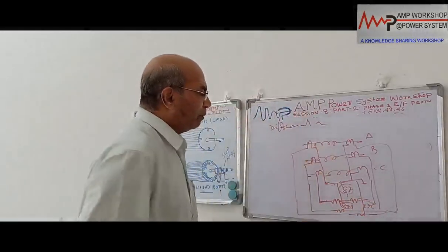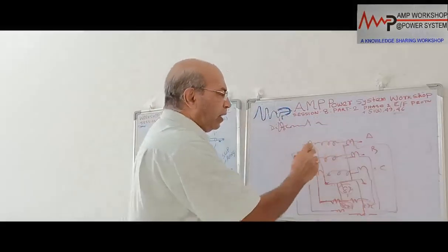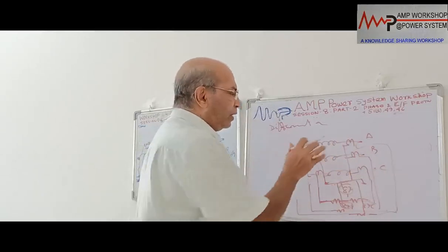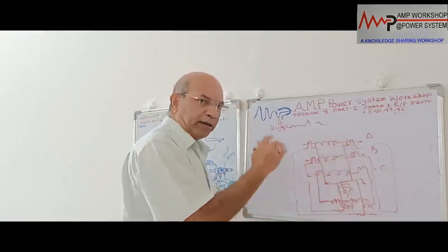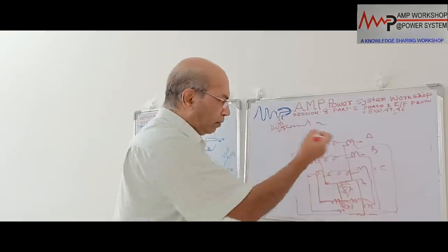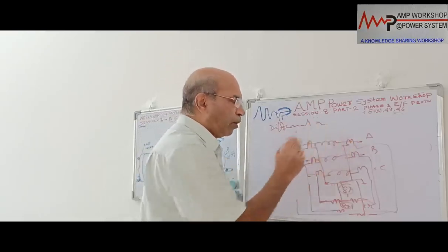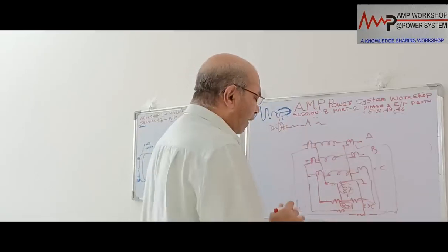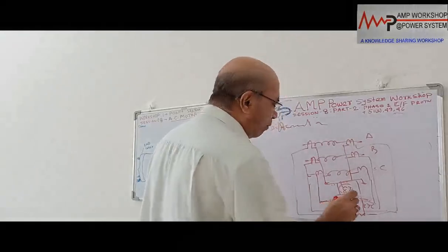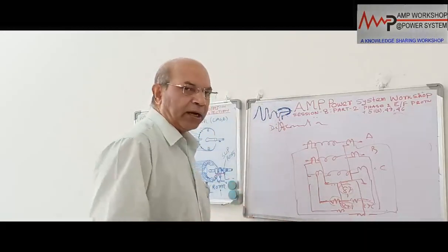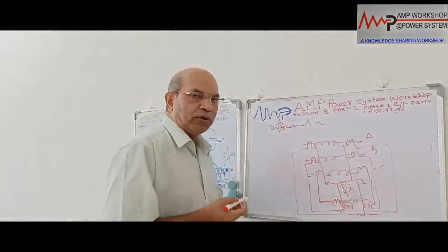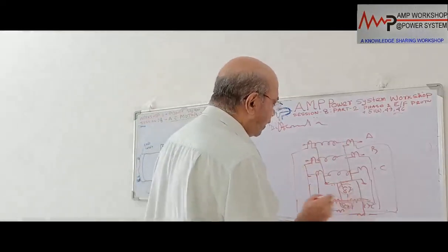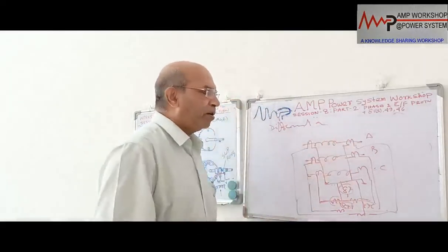So this will be the differential protection. In that case, all the CTs will be identical and high range, but CT saturation shall not be there. That is our consideration. The CT will be a PS class CT with a high burden, and the saturation point will be very high. So the CT will not get saturated, and then we will be using the restraining coil, the percentage restraint, to avoid the mismatch of the CT ratio or any spill current. That will not pass through the relay. It will pass through the restraining coil. Okay. So this is the basic principle of differential protection.